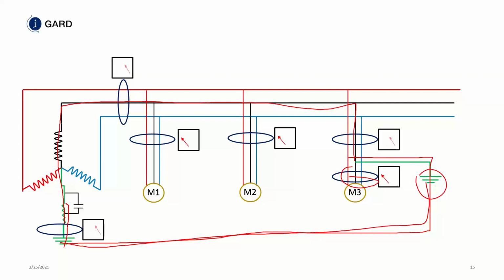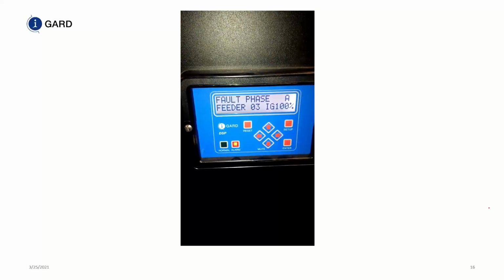Everything continues to work. This is why we have so many high resistance grounding systems in data centers all over the world, but we're discussing North America right now. We have some of our resistance grounding systems in some installations that claim that they will lose $1 million a minute if the power was shut off. So much so that the entire industry, that bank, would go bankrupt if there was 3 consecutive days of no power in that system. So they rely on this system.